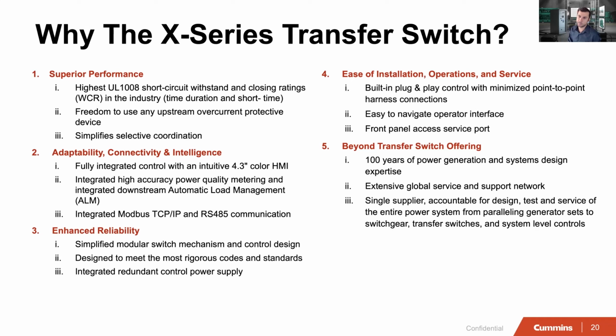Same thing with operation and service and installation, right? Plug and play control to minimize point-to-point harness connections. The easy to navigate screen for the operator. Front panel accessible for the service port, so we don't have to open up the transfer switch. If you have to open up the transfer switch while it's live, you'd have to suit up per safety requirements.